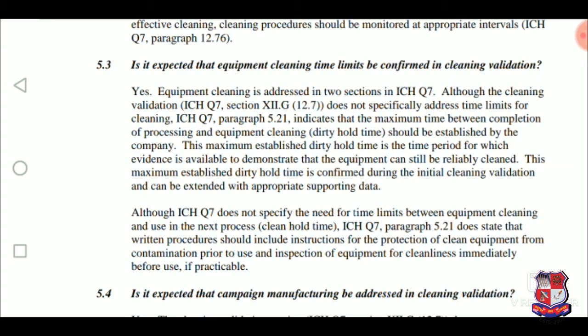Paragraph 5.21 indicates that the maximum time interval between completion of processing and equipment cleaning should be established by the company or the organization. This maximum established dirty hold time is the time period for which evidence is available to demonstrate that the equipment can still be reliably cleaned. This maximum established dirty hold time is confirmed during the initial cleaning validation and can be extended with appropriate supporting data.